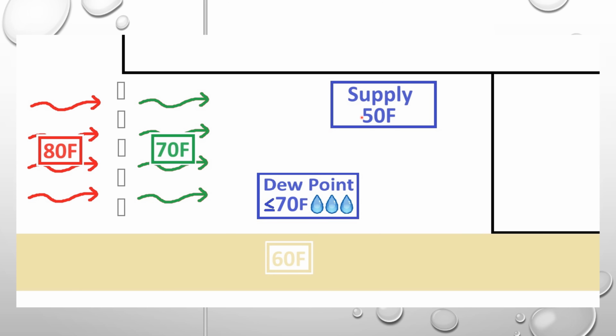Here's a supply duct, 50 degrees. This is our crawl space temperature of 70 degrees and our outside temperature of 80 degrees. So we're starting to build a diagram here. The next diagram we're going to do is what is the insulation around our ductwork, which is going to be R8, but what is the temperature of that insulation? That is a key factor here.